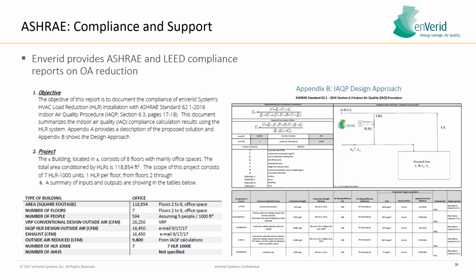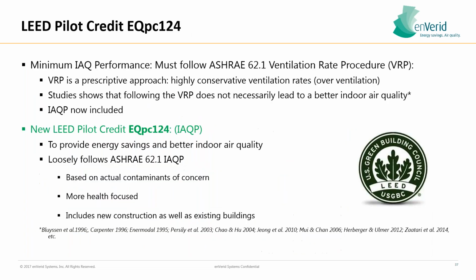This is a snapshot of the compliance report that EnVerid can run for you as well. Basically, all you do is provide your assumptions that would go into a ventilation rate procedure calculation, so occupancy, square footage, space type, and we can figure out how much outside air to reduce from that space. We spit out a compliance report, we show our calculations, we provide design integration suggestions, and you're off to the races. We also provide some assistance on LEED as well to make sure that those projects are successful.